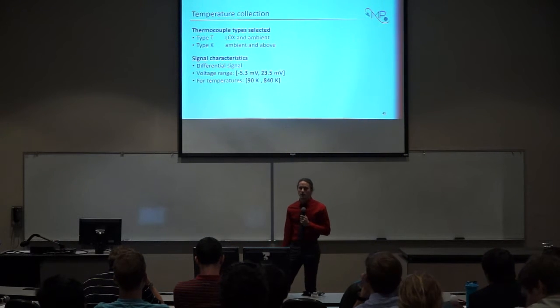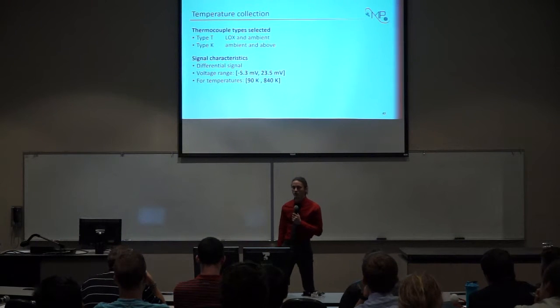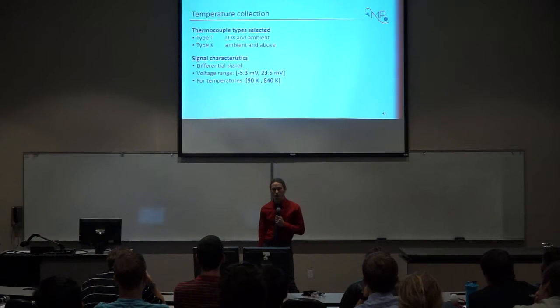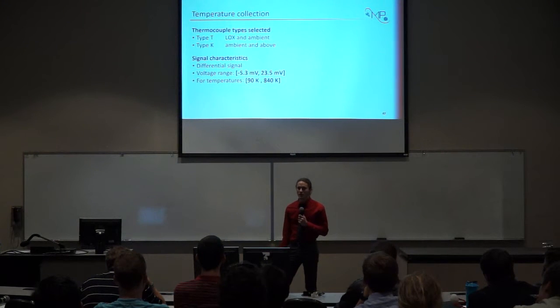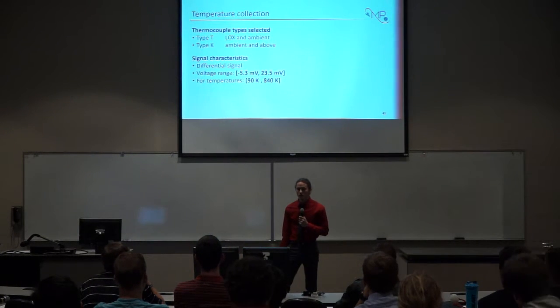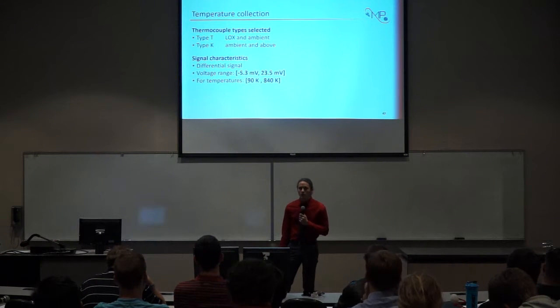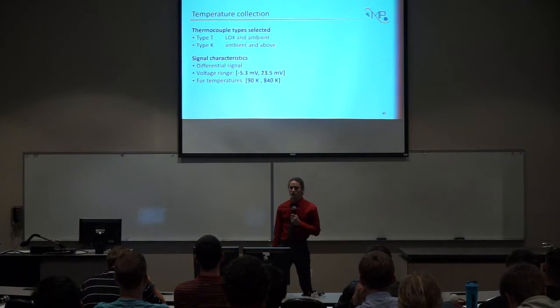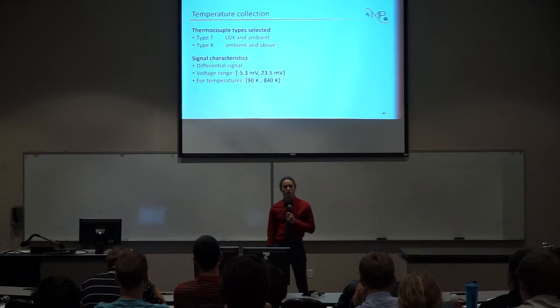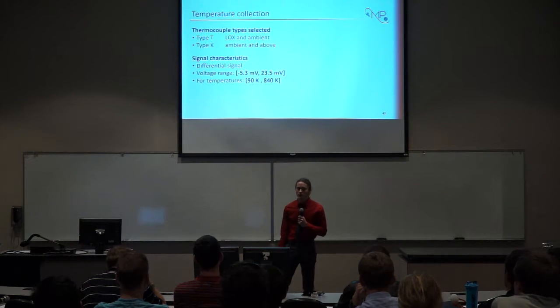In order to collect the temperatures that we are looking at, we went with thermocouples instead of resistive type temperature sensors because they're more robust to vibrations. And in order to get the temperature ranges that we're looking at, we're using type T and type K thermocouples. The type T will cover the LOX temperatures up to ambient, and then we'll use the type K for ambient and above. For the signal characteristics of the thermocouples, they're a differential signal in the millivolt range, and for the temperatures that we're looking at, it's going to be negative 5.3 millivolts up to 23.5 millivolts.